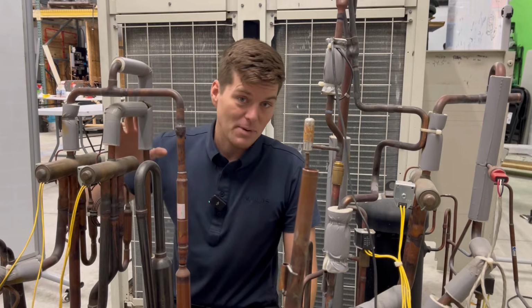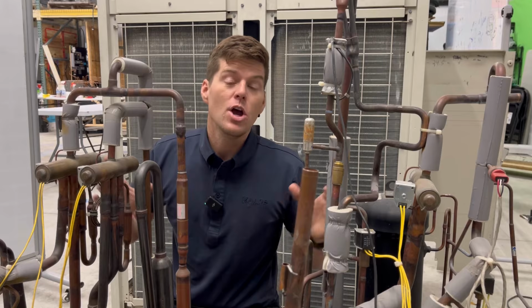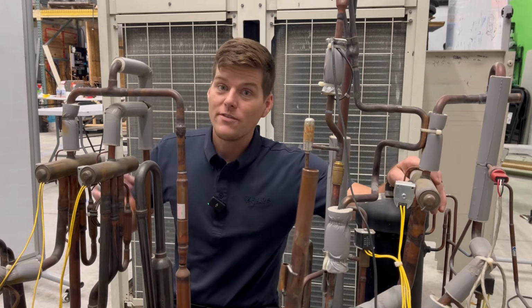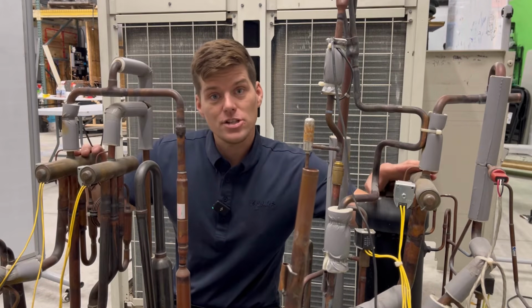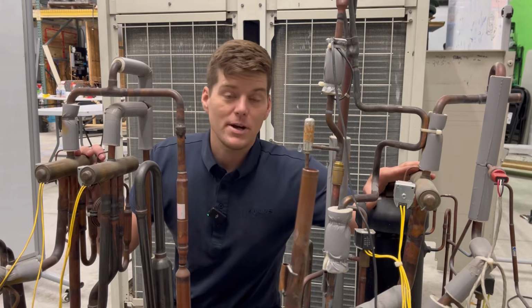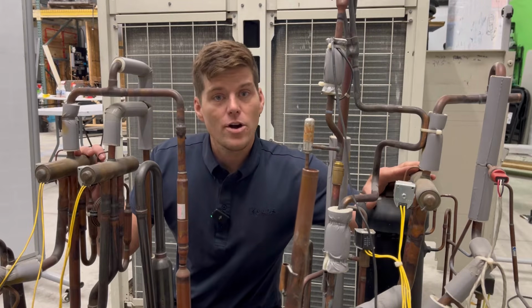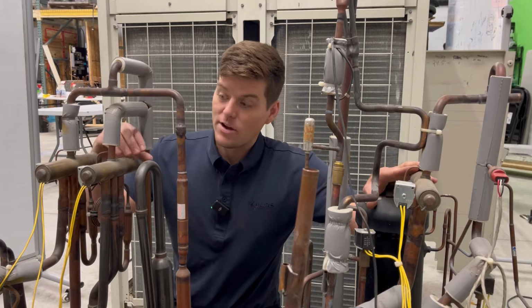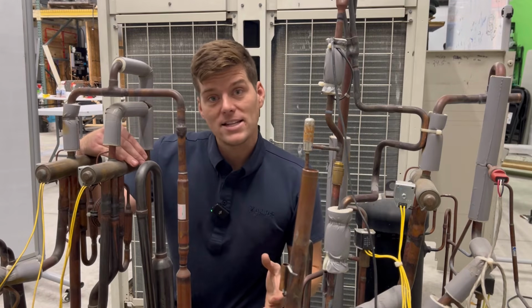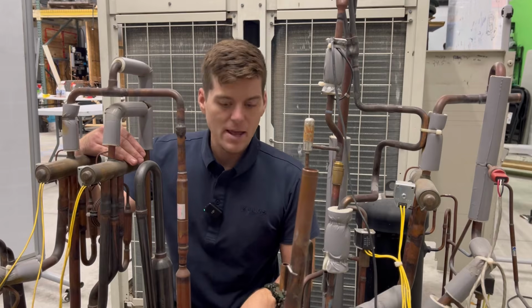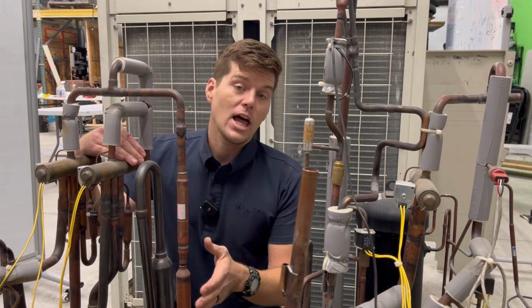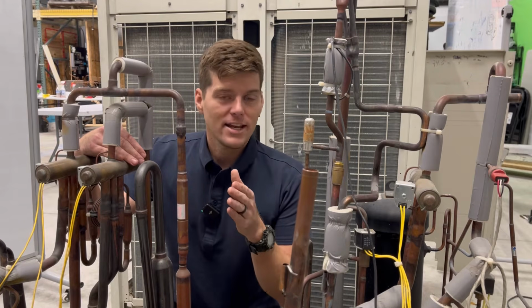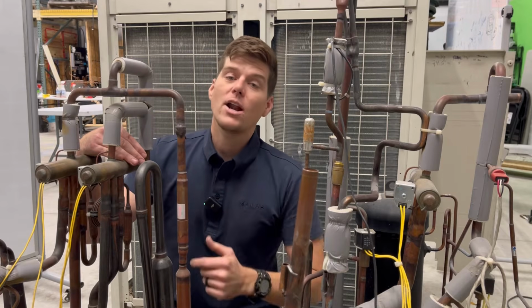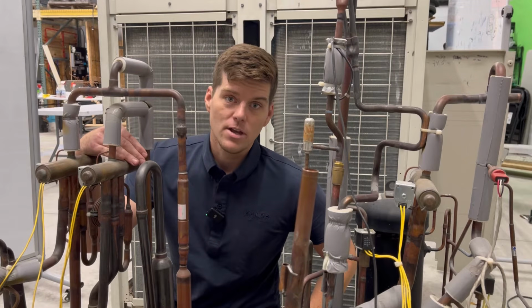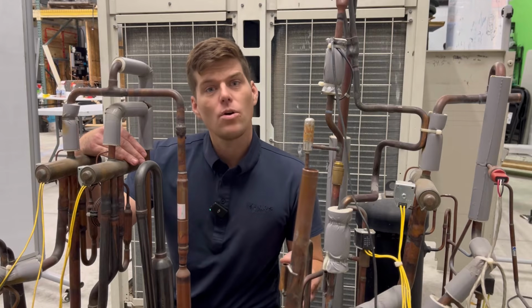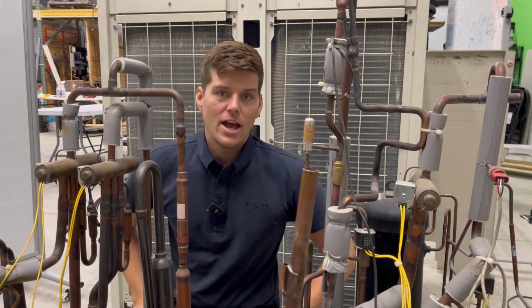We can get into the science behind it and how heat recovery works, but essentially we have two separate heat exchangers, one left, one right. There's a four-way valve dedicated just for the flow of refrigerant for those coils, whether it's in parallel operation, 100% heating, or 100% cooling. The last valve that we have here, the third one, is the actual dual gas line. This is the one that determines on three-pipe heat recovery whether that third line is a hot gas line or a secondary suction line. So let's get into how do we troubleshoot these and test them out in the field when we can't trust the service data or trust what we see on the actual service tools.